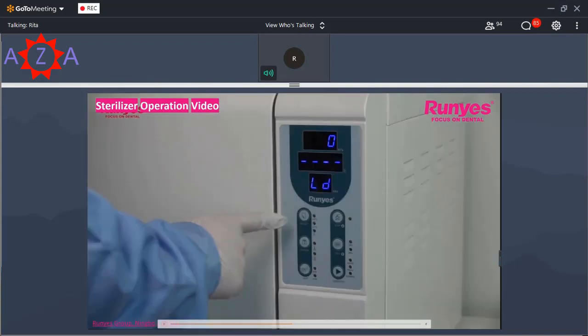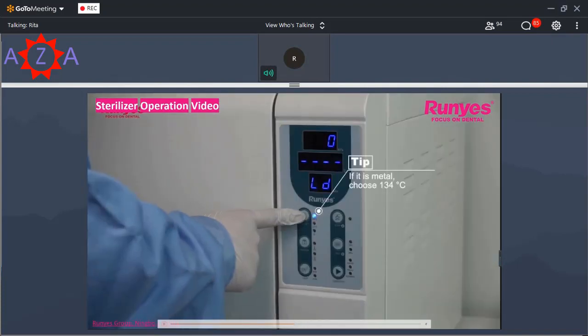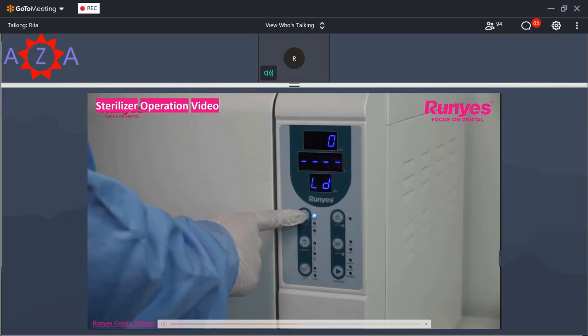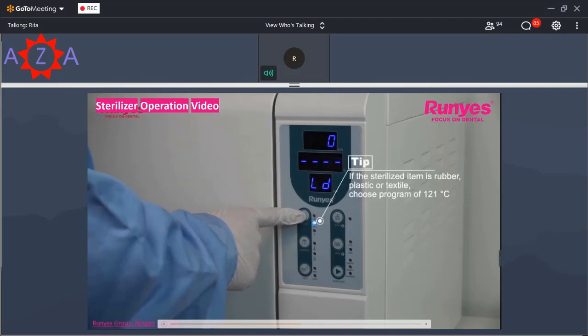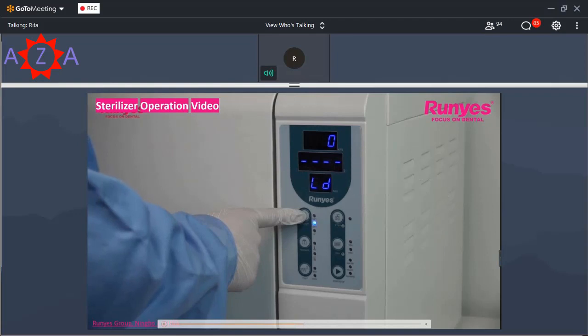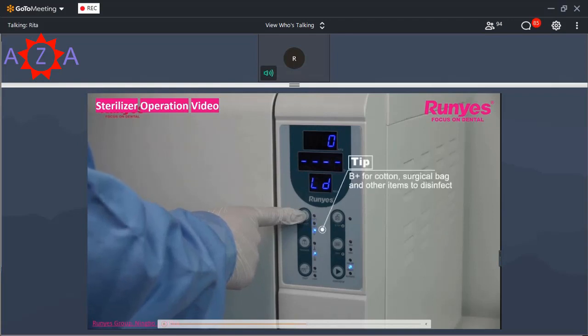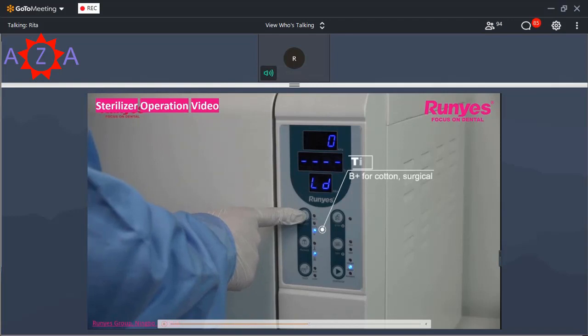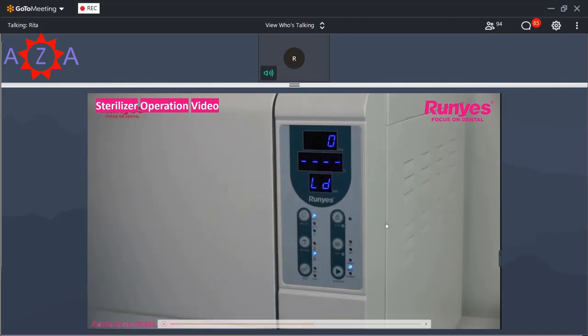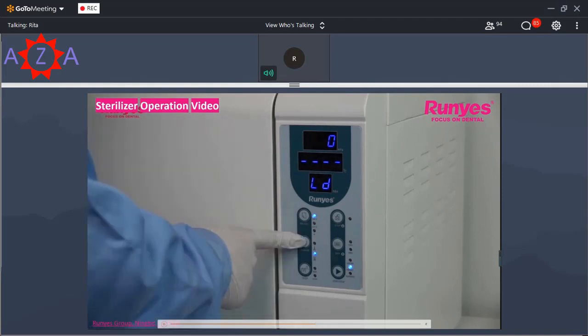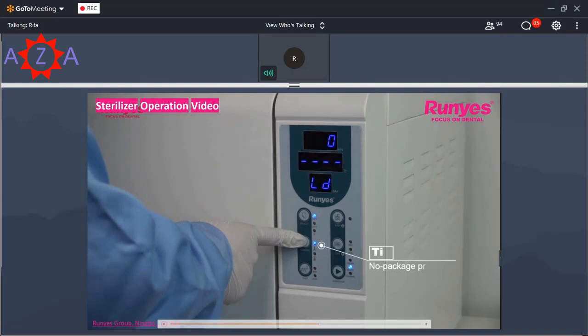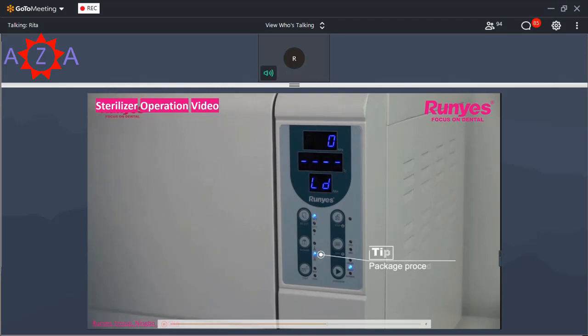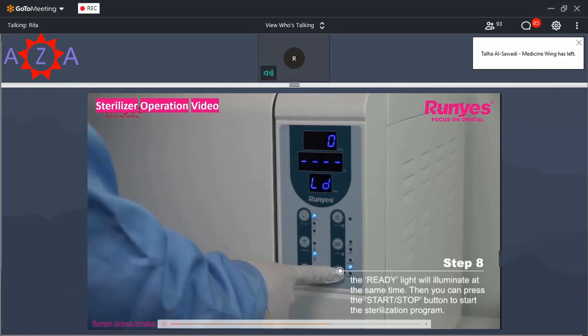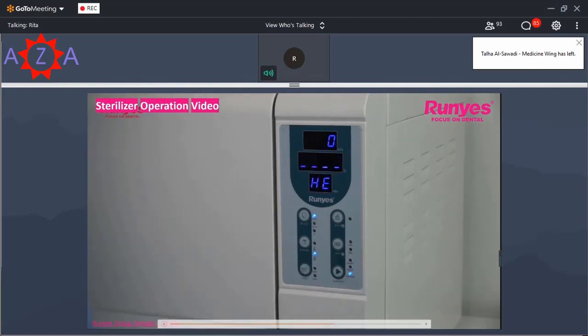Now we will select the cycles. Firstly, we select the temperature: 134, 121, and B plus program. For this one, we choose 134 degrees. And then we choose the instrument conditions, package or without package. Obviously, we need the package. After choosing the cycle, the light here shows ready, so we can run it by pressing start.